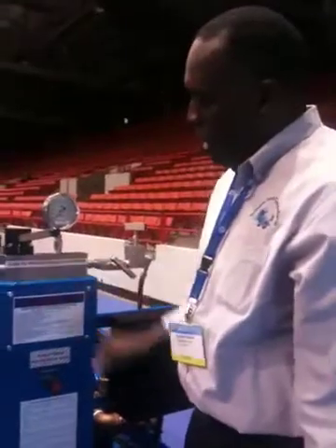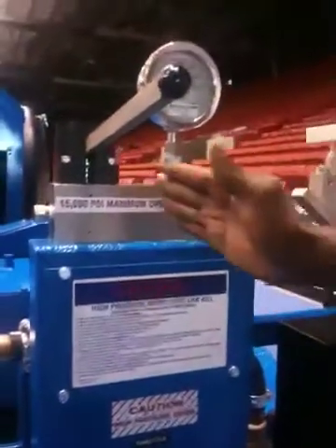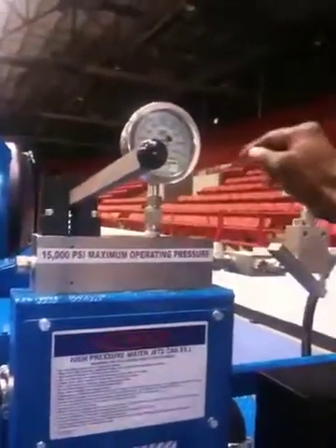This is what we call our 15,000 PSI pressure control valve. The pressure control valve body has two parts: it has a bypass side, and it also has a check side and a check-and-bleed side. We have our check valve system coming from the discharge side of the pump.